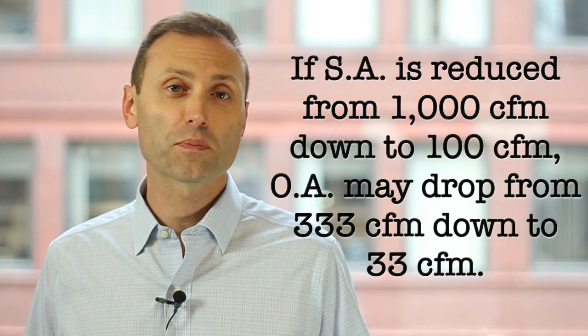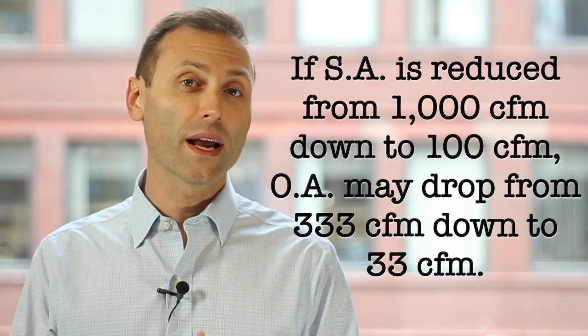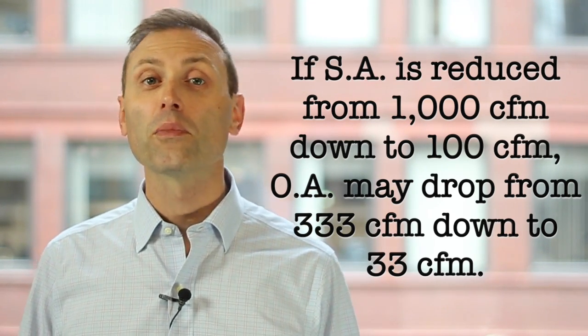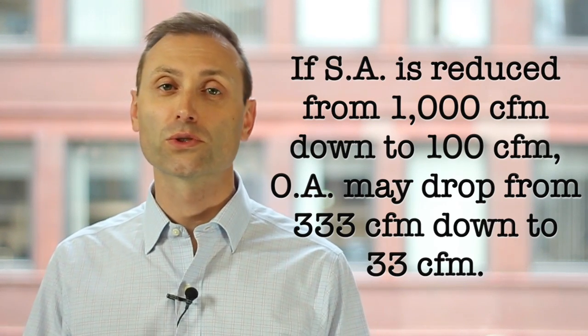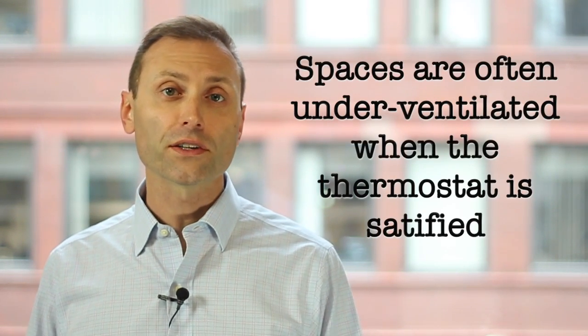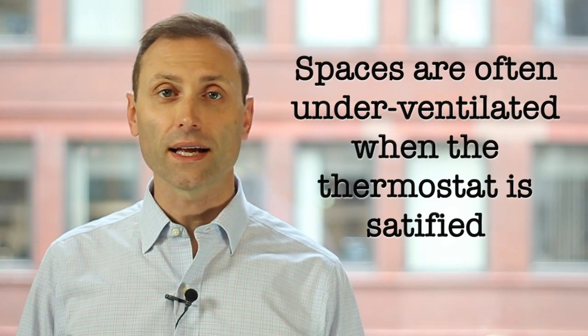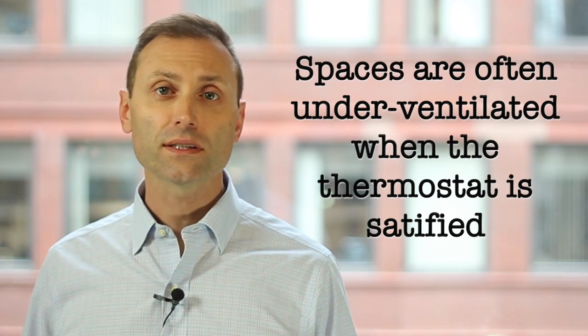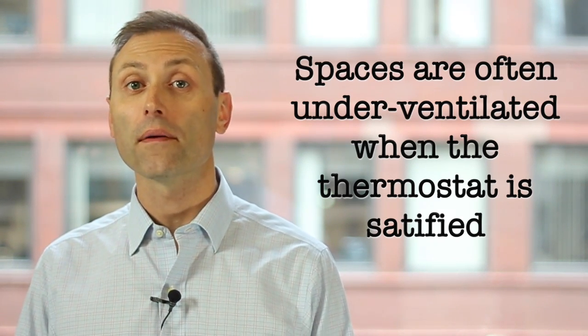The number of people in the space didn't change. The square area of the space didn't change, but the amount of ventilation was dramatically cut. To summarize, with VAV systems, spaces are often underventilated when the thermostat is satisfied. During these times, indoor air quality issues may be more likely to occur.